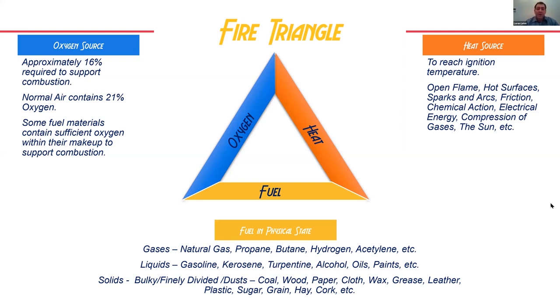One interesting thing about the fuel is we talk about different types of fuel, but for it to actually be involved in a fire, it has to be in the vapor state, and we'll talk about that a little more. With ambient air, we have 16% required for supporting oxygen, and that number is kind of critical when we talk about systems that monitor for less than 16% oxygen, such as 15%, in high value storage and things like that, where the fire can't sustain itself.